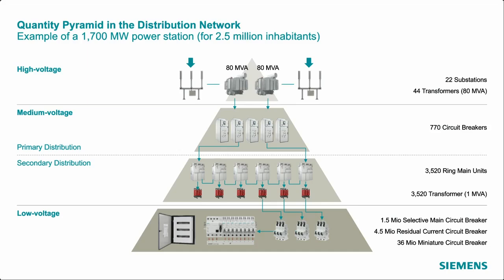For medium voltage, we will have, in primary distribution, 770 medium voltage circuit breakers. Just a small quantity of these circuit breakers will be used as main feeders to protect the transformer located upstream. The rest of the circuit breakers will be used as feeders to distribute the electricity downstream.